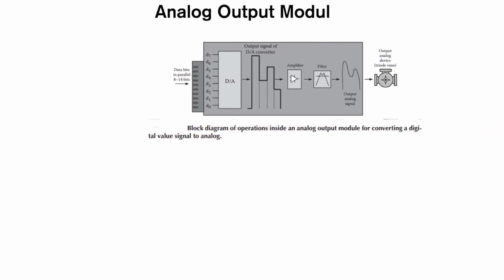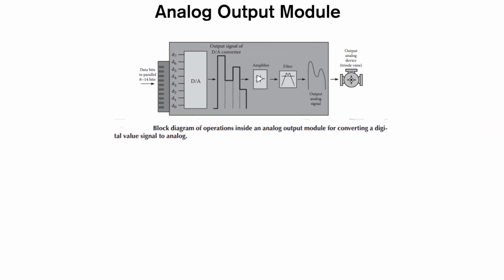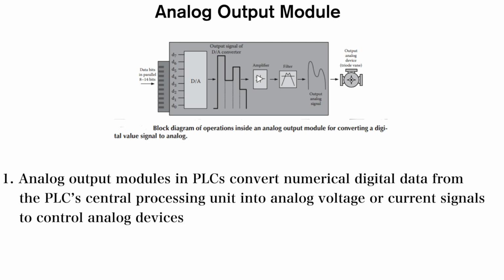Now comes the analog output module. An analog output module in a PLC converts the numerical digital data from the programmable logic controller's central processing unit into an analog voltage or current signal to control analog devices. You can see the block diagram of operation of the analog output module, converting a digital value signal to analog.